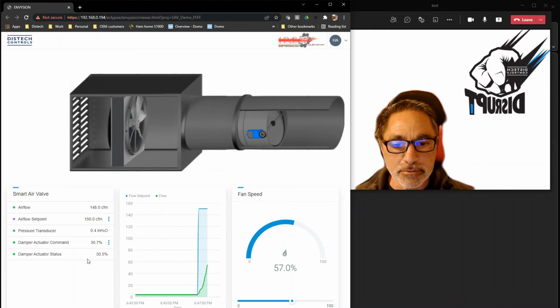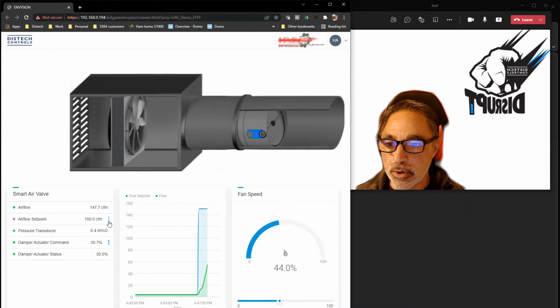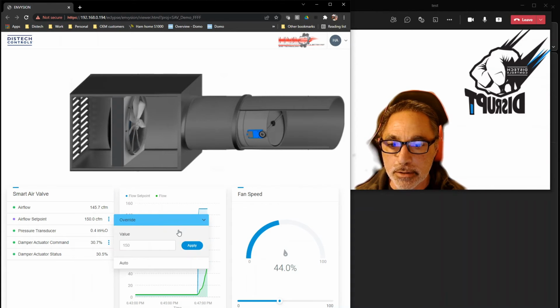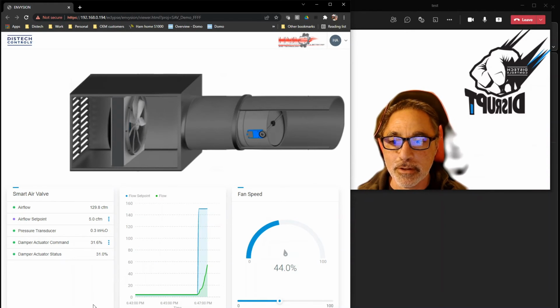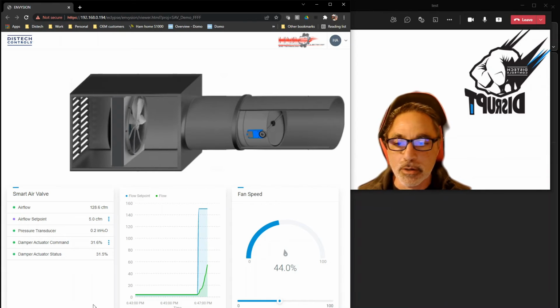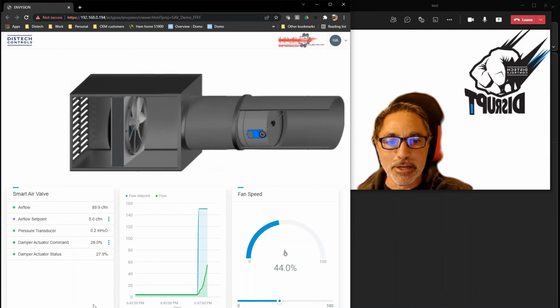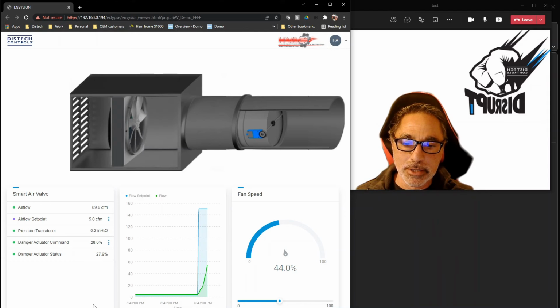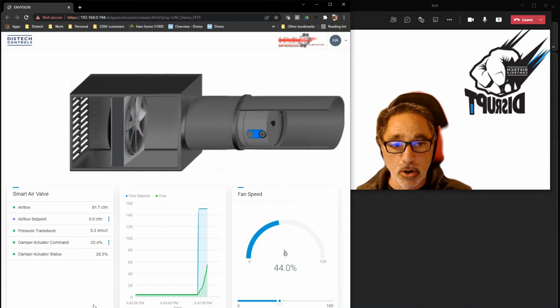So for the sake of time, let's go ahead and reduce the CFM just a tad. I'm going to override this and take it down to 5 CFM. Now, I'm not sure if a lot of people have seen this before, but 5 CFM is a very low CFM. Back to the ASHRAE standards that we talked about, when you're in the unoccupied period, there are standards telling all the manufacturers to go to those low CFM.